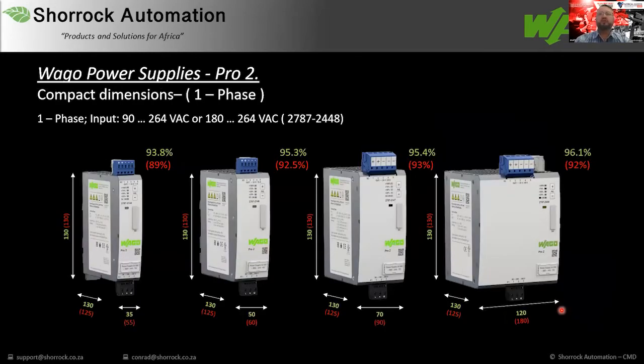So in green, you will see at this point here, the physical size of the WAGO power supply. This is our 5 amp power supply at only 35 millimeters wide. And we've done a product evaluation with a few competitors out in the market, and we found that the average size on the competitor product range for a 5 amp power supply is 55 millimeters. That means our power supply is 20 millimeters less in width. This power supply has an efficiency of 93.8%. The average on our competitors on this is 89%.